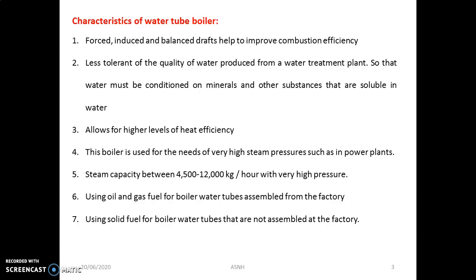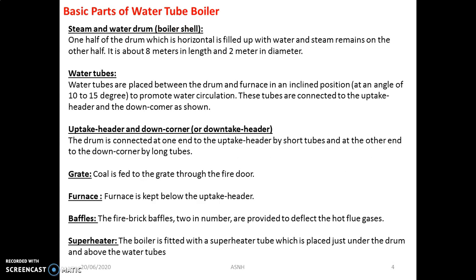Let us look at the basic parts of the water tube boiler. The first is the steam and water drum, also called the shell. It is about 8 meters in length and 2 meters in diameter, made of stainless steel material which is corrosion resistant. The water tubes are also made of corrosion-resistant materials — sometimes mild steel and sometimes stainless steel are used. The tubes are inclined at an angle of 10 to 15 degrees.